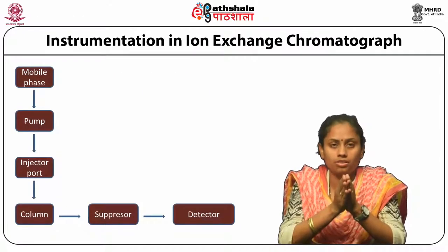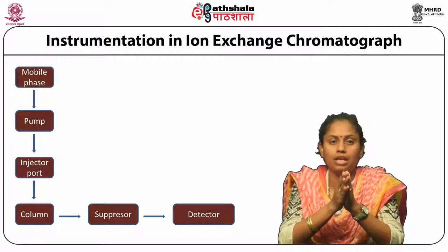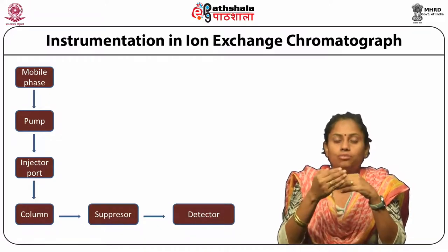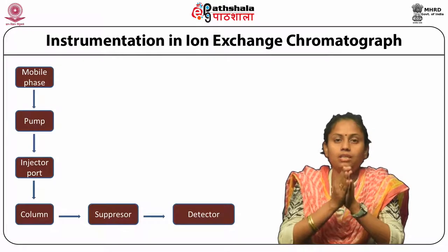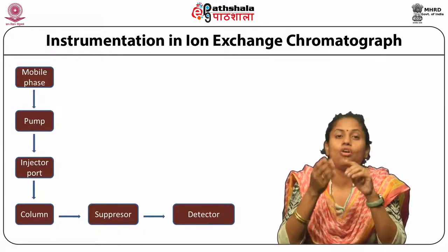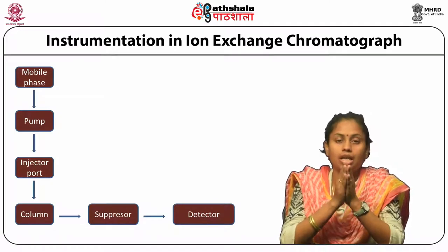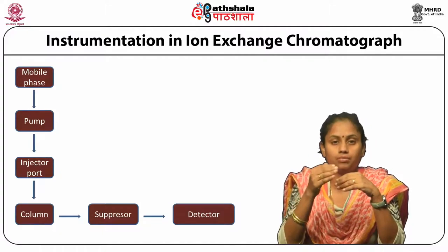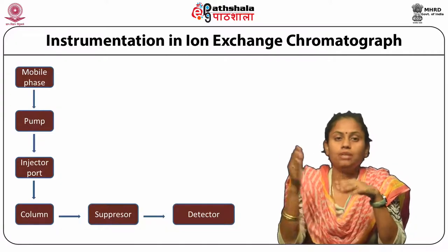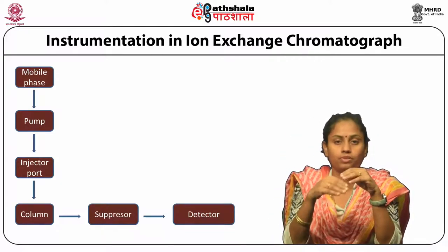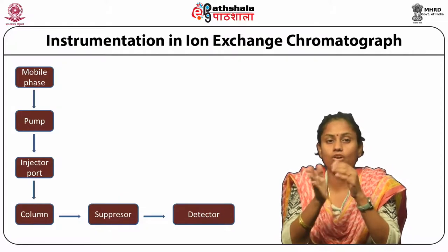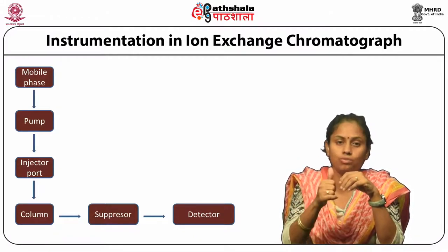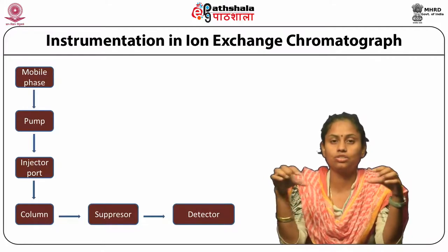The basic components of an Ion Exchange Chromatograph are shown in the picture. Now let me tell you how the Ion Exchange Chromatograph is operated. The mobile phase, which comprises of a buffer or a solvent system, is introduced into this chromatograph system by the high pressure pump. The pump pushes the mobile phase into the next component by the exit non-return valve. The sample is then injected through the injector port.